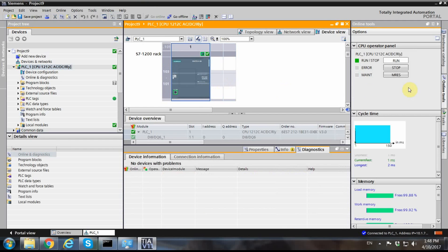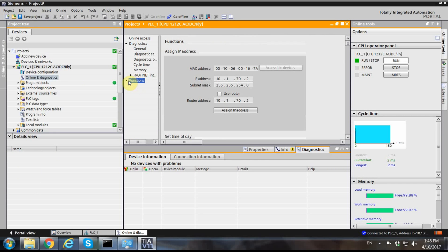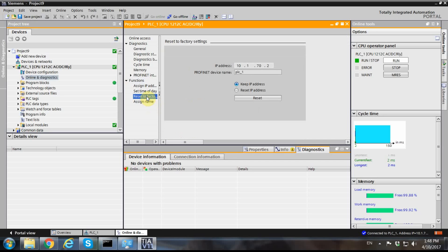Going online again, I can stop or run the PLC as before. In the Online and Diagnostics section you can see the newly assigned IP address. If you want, you can reset it from the list of functions — either keeping or discarding the IP address. So the workflow is: change your PC's IP to match the PLC's subnet, connect and go online, then optionally reset and reassign. I hope this is helpful — thank you for watching and see you next time.